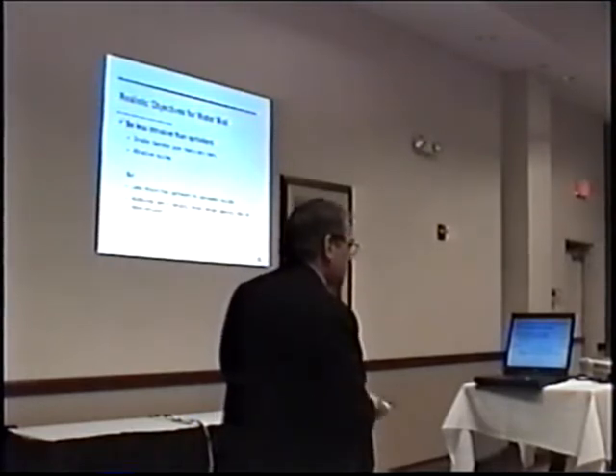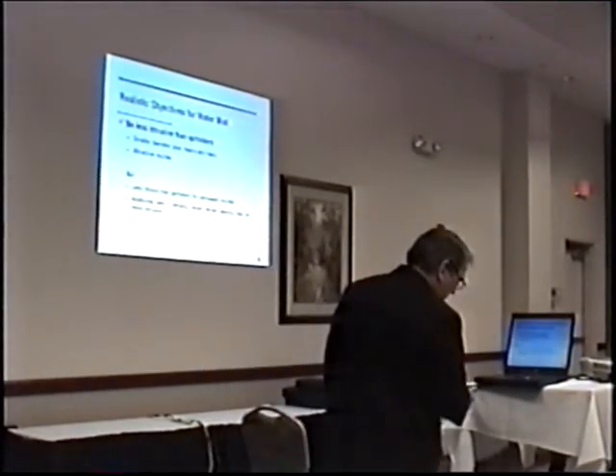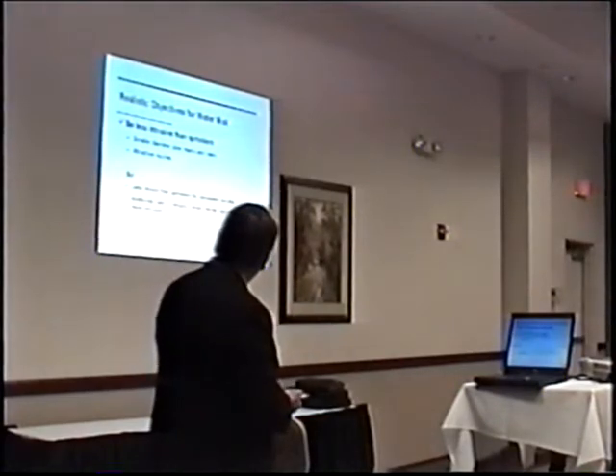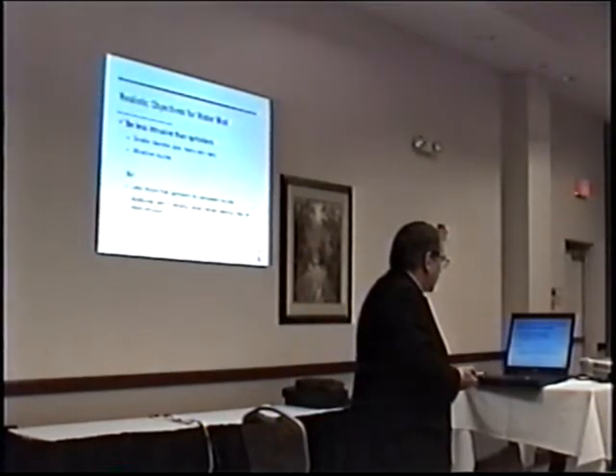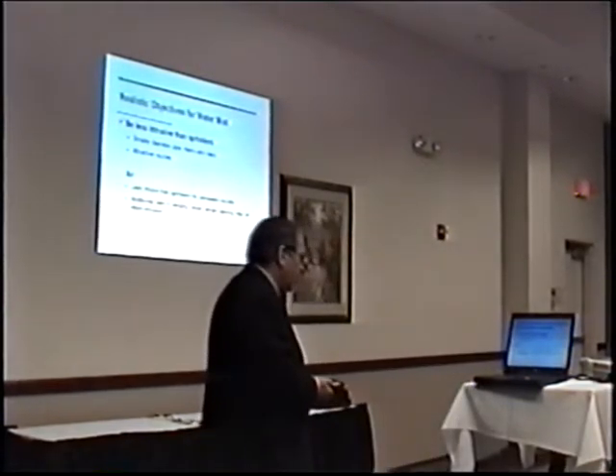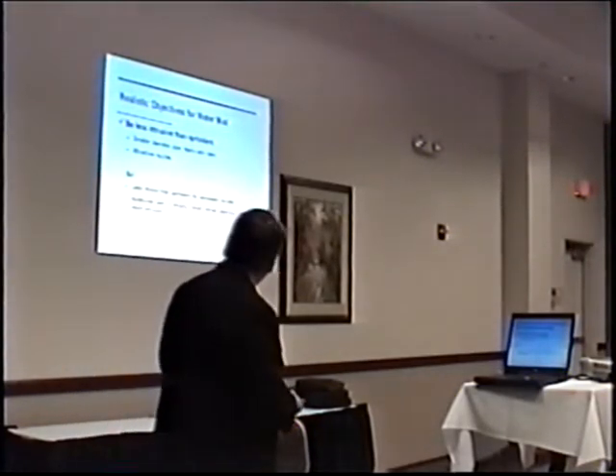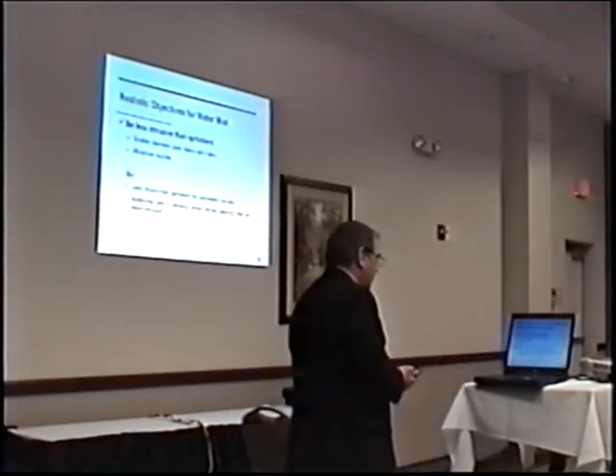How about the fact that water mist systems might be less intrusive than sprinklers? Instead of having 4-inch pipe and 3-inch pipe in the walls of the building, we might only have 1.5-inch or even 1-inch pipe in the building. And it is true that pipe can be less intrusive than sprinklers. One of the things I'll bring out with the National Gallery of Art, there are some disadvantages. There's a lot less choice in the type of sprinklers that you might want to use in terms of architectural finish and that kind of thing. And the additional care, particularly for a high-pressure system, the additional care taken for the hangers and the closer hanger spacing actually may mean that you're doing more intrusive work in the building than with standard sprinklers.